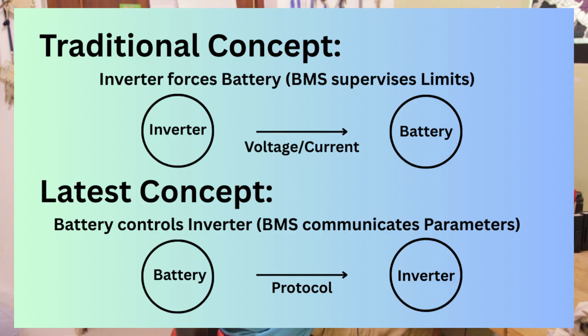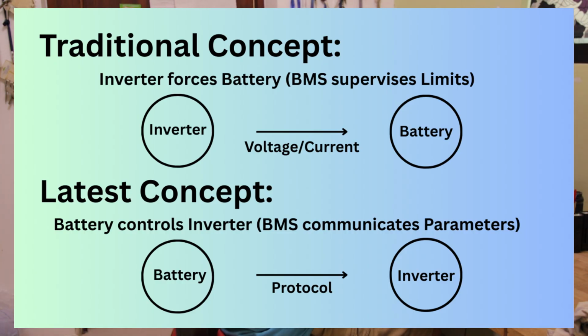The traditional concept is where the inverter, or you can also just say a charge controller, is forcing the battery, and the BMS, which is built into the battery, is just supervising the limits, and once a limit would be breached, then the BMS would discontinue the operation, which normally, if the settings on the inverter or the charge controller are right, would never happen. So the inverter is controlling voltage and current and charging or discharging the battery.